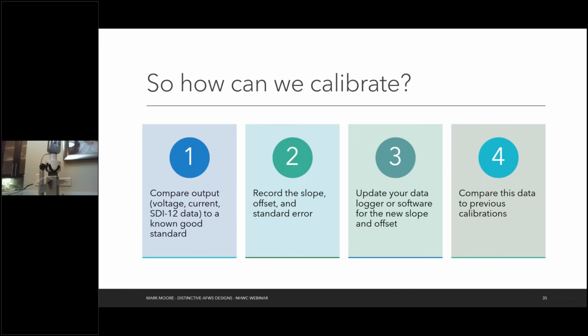So how do we actually calibrate? Now we know why, and we know what can impact it. How do we actually do it? Well, we're going to compare an output, a voltage, a current, or an SDI12 data to a known good standard. We're going to record that slope, offset, and standard error. We're going to update our data logger or software for the new slope and offset, and we're going to compare this to previous calibrations.